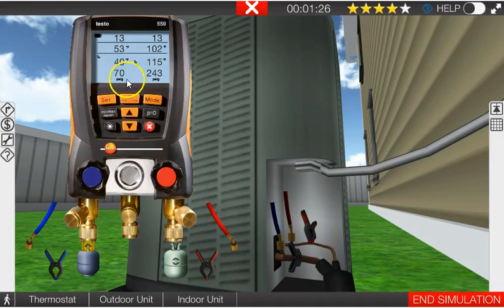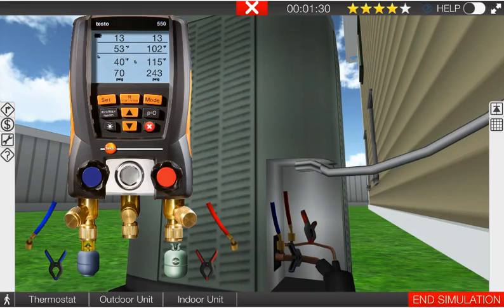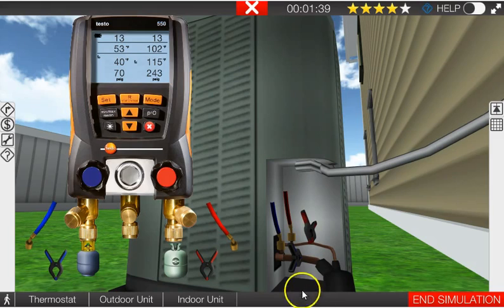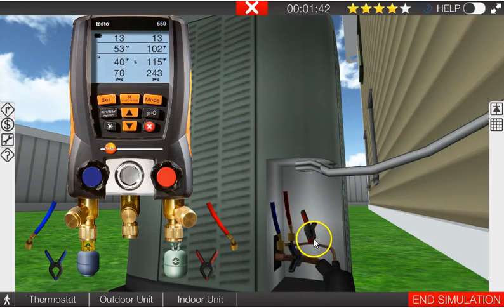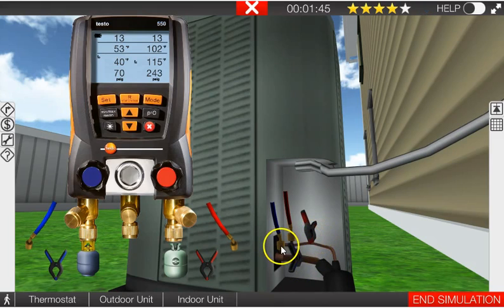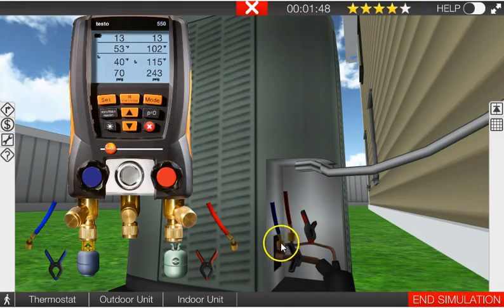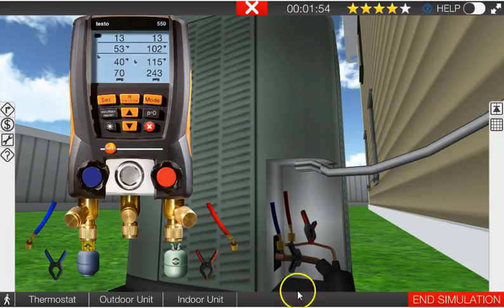And the 70 PSIG, I want you to transport yourself into the evaporator coil. That is taking a snapshot of what's happening on the inside of the evaporator coil. And then when you have your temperature probes and look at those, those are measuring the physical temperature right here. So even though these hoses and the temperature probes are close together, these hoses are actually telling you what's happening in the center of both of the coils.